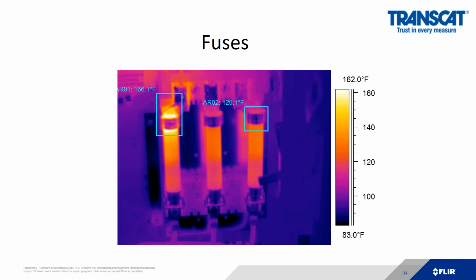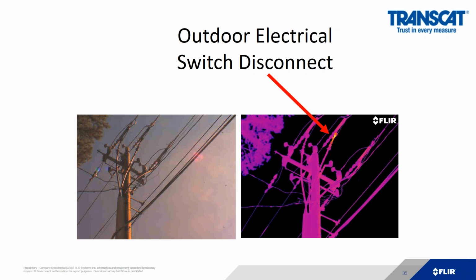That is the beauty of infrared. It allows you to defeat Murphy's Law, that common expression, when things go bad, they go bad at the wrong time. When things go bad, they didn't go bad immediately. They've been going bad for quite some time. All problems don't go from being fine to bad in an instant. It's a gradual time. So by using thermal imaging, you'll be able to find these problems before they become critical and cause a plant fire.